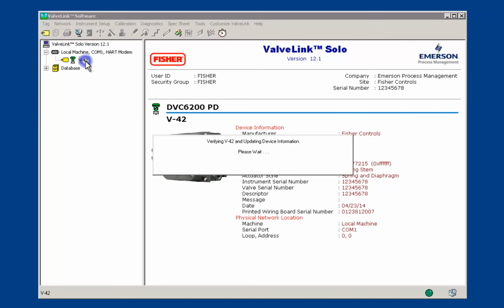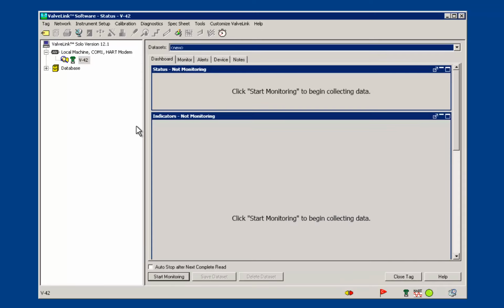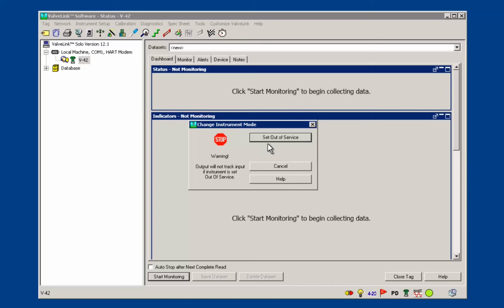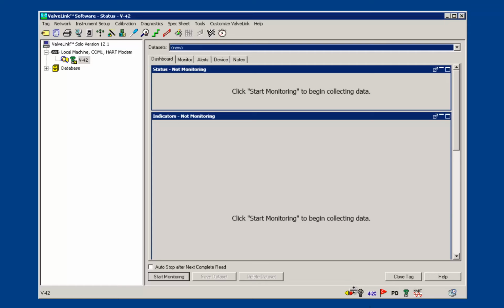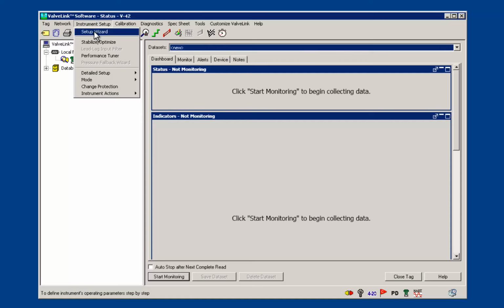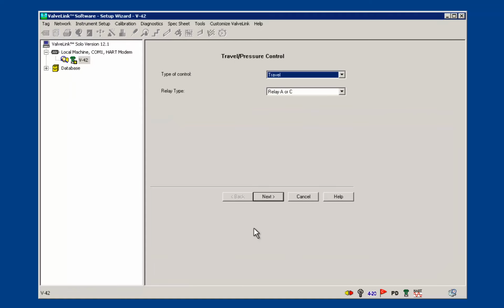If the instrument is in service, as indicated by the yellow icon at the bottom, take it out of service before getting started. Click the Instrument Mode button and click Set Out of Service. Once the light bulb icon at the bottom is dark, go to the menu bar option Instrument Setup and then go to Setup Wizard. First, decide what type of control you want to give the instrument.